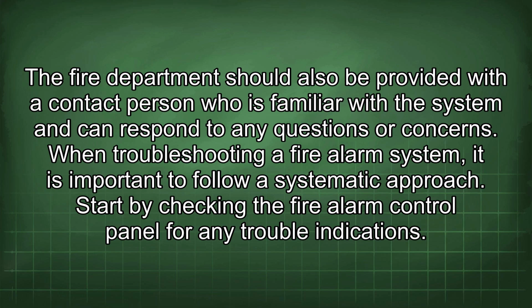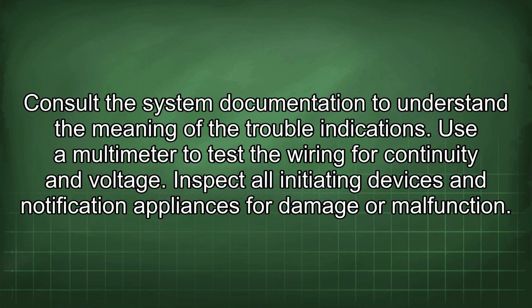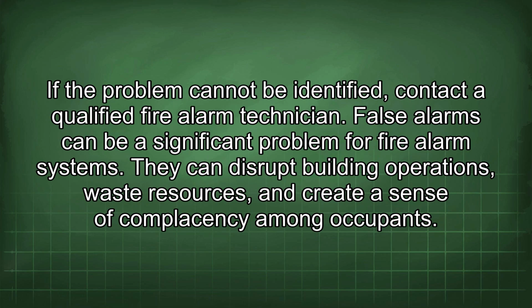When troubleshooting a fire alarm system, it is important to follow a systematic approach. Start by checking the fire alarm control panel for any trouble indications. Consult the system documentation to understand the meaning of the trouble indications. Use a multimeter to test the wiring for continuity and voltage. Inspect all initiating devices and notification appliances for damage or malfunction. If the problem cannot be identified, contact a qualified fire alarm technician.